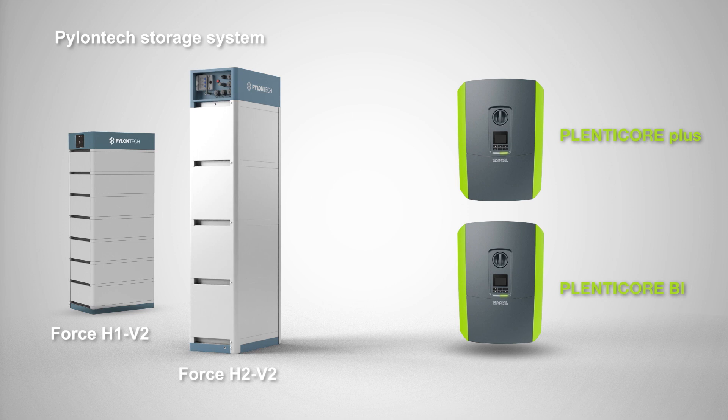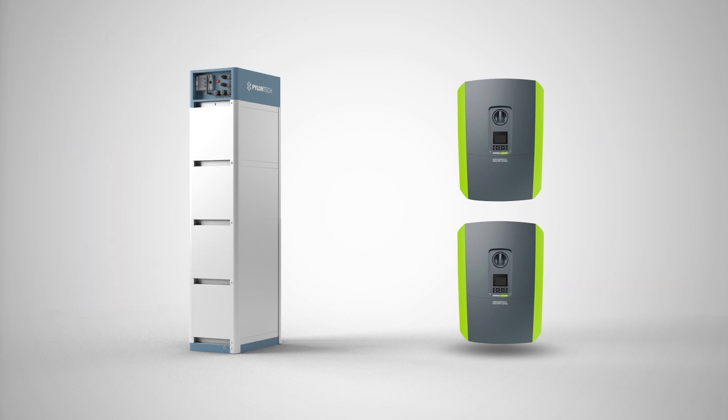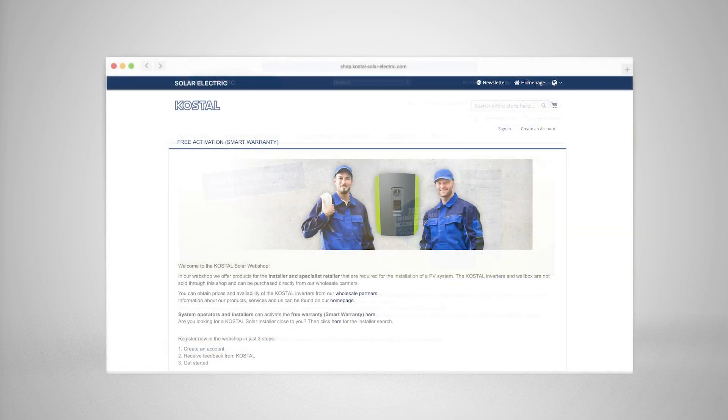Please note the instructions for intended use. To operate a battery system such as Pylontech Force H, install the Kostal Smart Energy Meter beforehand. If you want to connect the Pylontech battery to a PlentiCore Plus, you will also need a corresponding activation code for battery activation. You can purchase this in the Kostal Solar Electric Web Store and activate it via the Kostal Web Server.